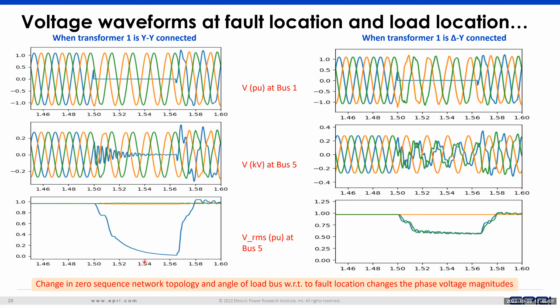Because of these differences in the transformer winding configuration, you can then really get an understanding of how DER would trip. So here in this example, when the transformer is star-star connected, the fault on one phase on the transmission network impacts only one phase at the distribution end. Whereas when the transformer is delta star connected, the fault on one phase on the transmission network impacts two phases on the distribution network, but the impact on each phase is not as drastic as the impact on that phase when the transformer was star-star connected. So we can utilize this kind of information to derive rules of thumb and approximations with respect to how DER would behave for these transformer configurations.